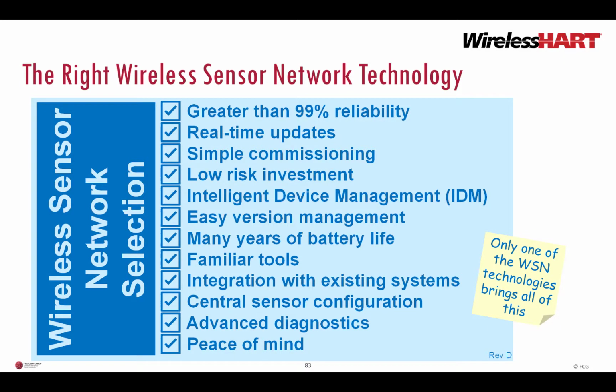That is, the WirelessHART technology is the most reliable, can be fast when you need it to, is the easiest to commission, is an international standard, so low risk. You can use the same IDM software as for wired instrumentation if you like, has long battery life. You can use the same field communicator as for wired instruments. Data integrates with your existing DCS, PLC, historian, and other software. You can centrally configure sensors, and you can access advanced diagnostics like vibration spectra. Other wireless sensor network technologies cannot achieve the same result.